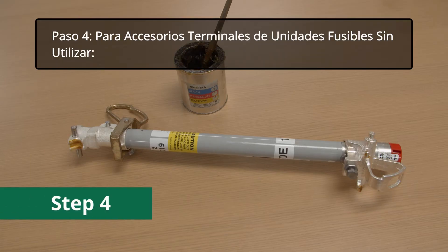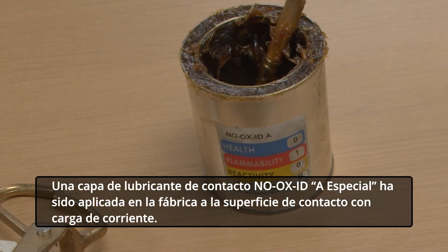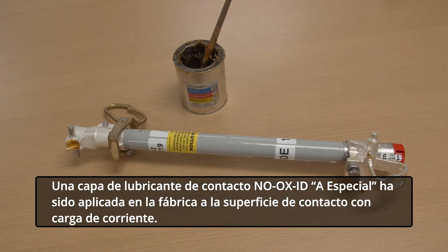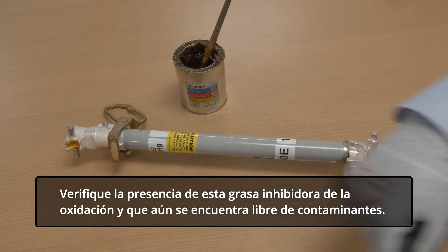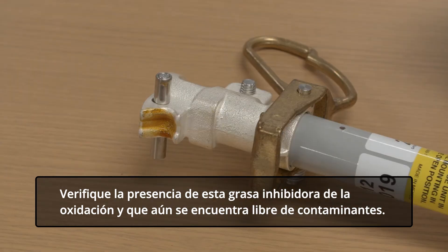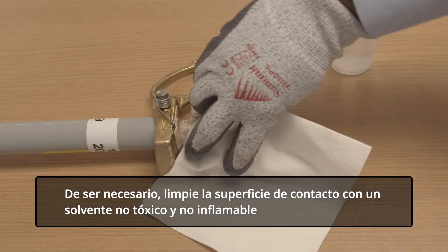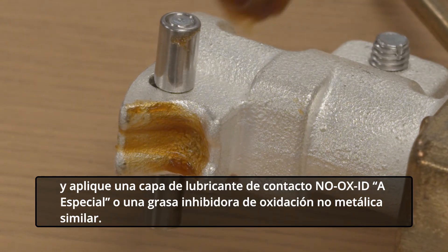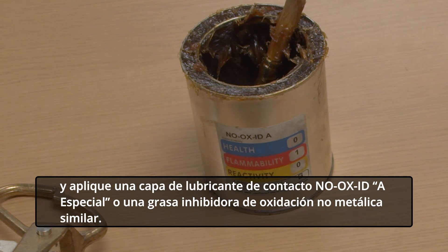Step 4. For unused fuse unit end fittings, a coating of No Oxide A Special Contact Lubricant has been factory applied to the current-carrying contact surface. Verify the presence of this oxidation-inhibiting grease and that it is still free of contaminants. If necessary, clean the contact surface with a non-toxic, non-flammable solvent and apply a coating of No Oxide A Special Contact Lubricant or similar non-metallic oxidation-inhibiting grease.